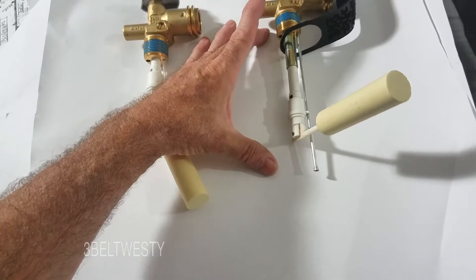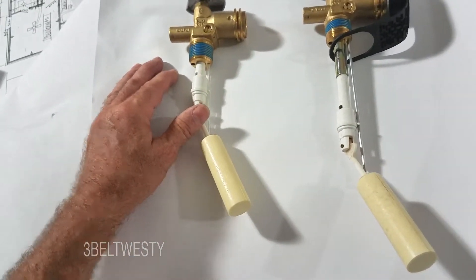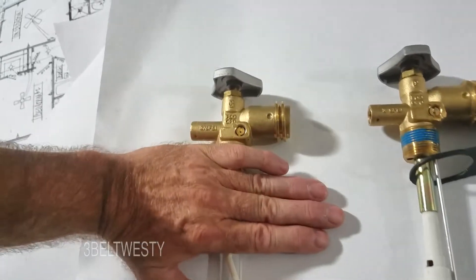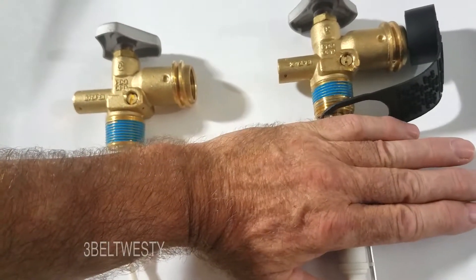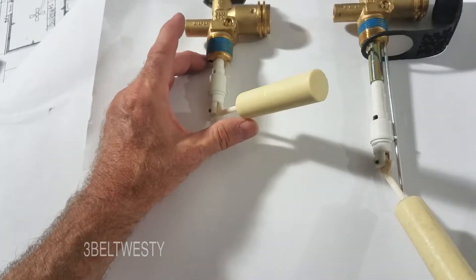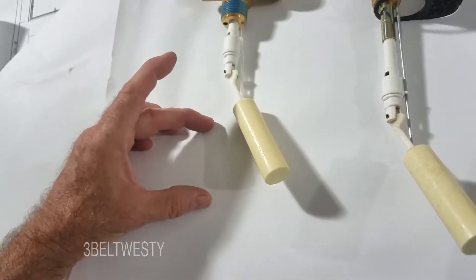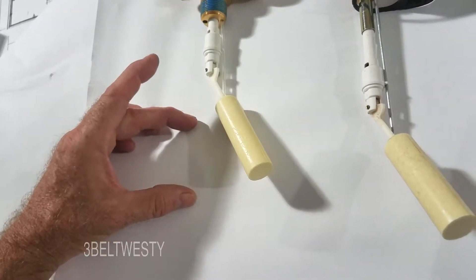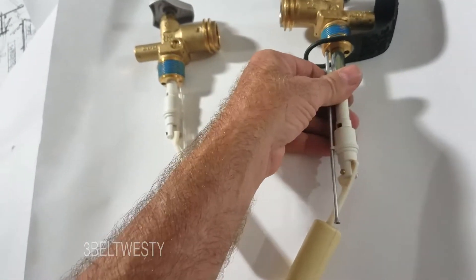On a tank from the top view, the valve looks the same. It's just what is inside. When you buy one of these or when they rebuild them, the float is actually down deeper in the tank cylinder. Those are cylinders because they have a shelf life generally of 12 years before they're inspected, and then recertification I believe is five years.